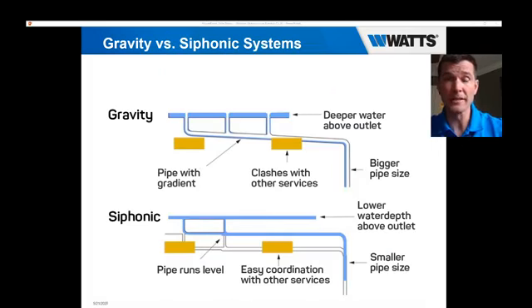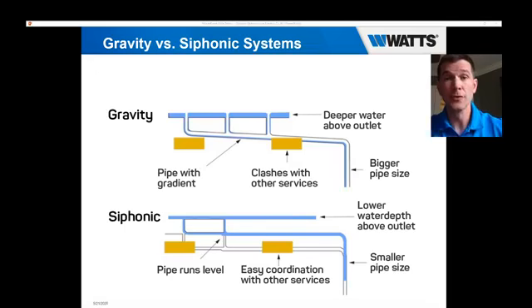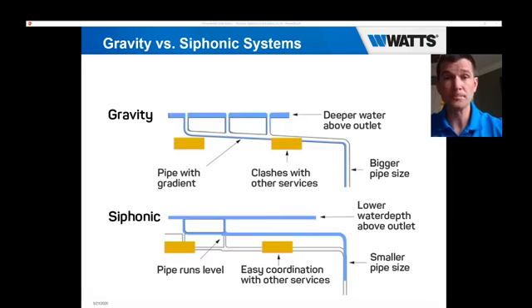Here are the two systems side by side. With a gravity system, you have a deeper water level or ponding on top of the roof compared to the siphonic. The difference with gravity is that to get everything down, you need to slope the piping through the system. This slope changes the angle of the piping through the building, making it more difficult from an engineering and installation standpoint to get around other services — other piping, vent work, and so forth.